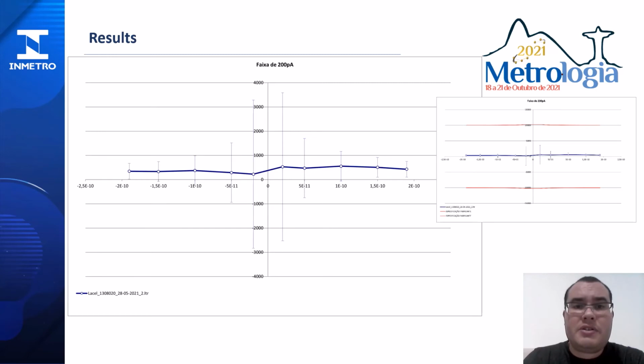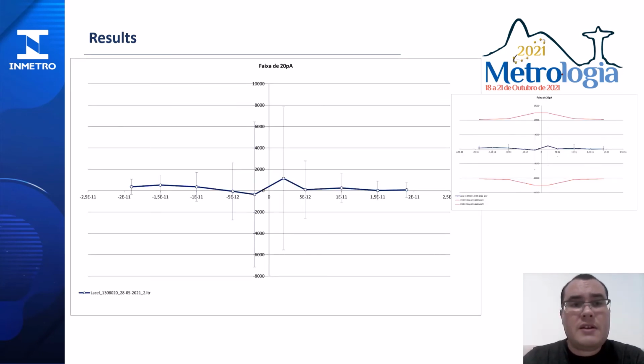This next range is the 200 picoampere range, with satisfactory values and uncertainty lower than the manufacturer's specification. Finally, the lowest range available on the calibrated equipment, the 20 picoampere range, also has lower uncertainties than specified by the manufacturer. With that, we can conclude, seeing all the ranges, that the calibration system using the Ohm's law method was implemented and reaches the necessary values for the calibration of the electrometers used in the SEMETRO area.